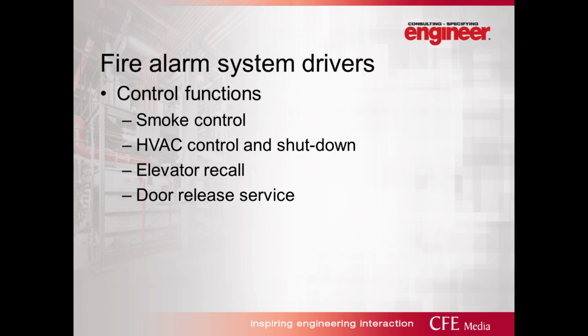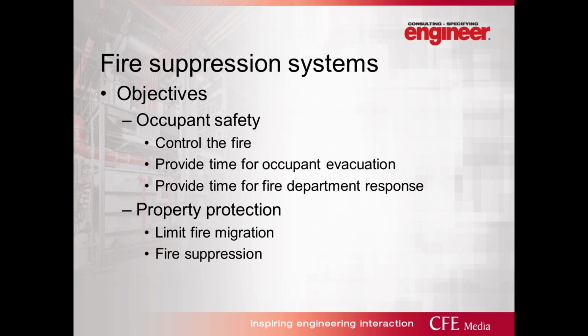Yeah, we also might have things like door release service where, say in an industrial facility, we have firewalls or fire-rated compartments for some reason. We might have doors on hold opens to facilitate flow of product and whatnot. That might be a case where we would put a fire alarm system in to control the release of those doors.